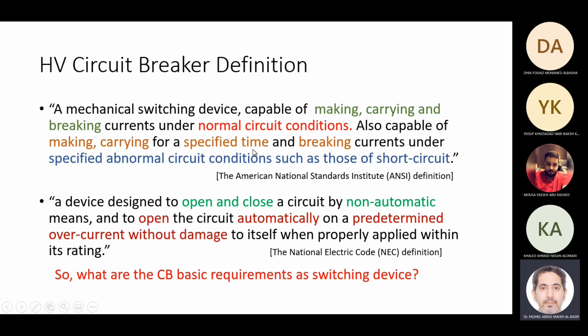At the end, when there is a short circuit, the breaker is not designed to carry that short circuit current for an indefinite time. Breakers are always specified with a breaking capacity for a duration of time. So there is a 1 second rating or 3 second rating that the breaker can handle while it is in a closed position during short circuits. So this is the definition of a breaker. There is nothing mentioned here about protection. It's a mechanical device. So in the high voltage system, this breaker needs a command from a relay or a protective device to open it.